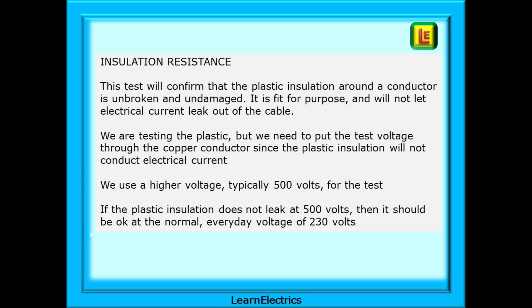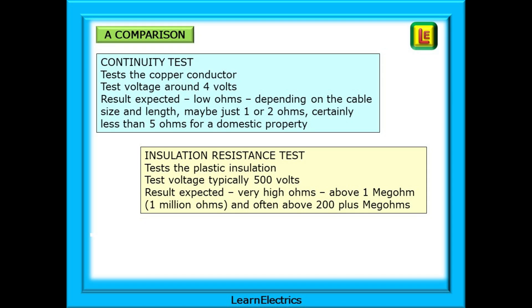We use a higher voltage, typically 500 volts, for the test on the assumption that if the plastic insulation does not leak or break down at 500 volts then it should be okay at the normal everyday voltage of 230 volts. So a quick recap on the two tests before we delve a little deeper.